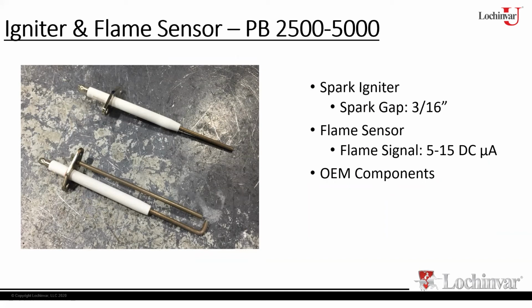All right. Now, because I have an igniter and a flame rod, one of the things that you typically don't do with an HSI is clean them. You might blow some stuff off of it if there's some buildup on it, but you never want to touch the igniter portion of it because you don't want to get the oils from your hand on the igniter or break the igniter. But when you're looking at a flame rod or the igniter and you get carbon buildup on them, you do want to clean them from time to time. Use something like a Brillo pad or Scotch-Brite pads.